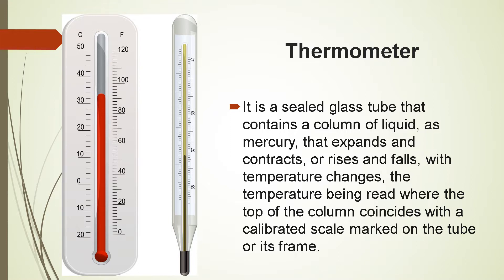When the bulb is inserted into the object, depending upon the temperature of the object, the mercury will expand or contract. When the mercury expands, its level rises in the capillary tube, and when mercury contracts, its level falls down in the capillary tube. The level of mercury in the capillary tube is read where the top of the column coincides with the calibrated scale mark on the tube or its frame.